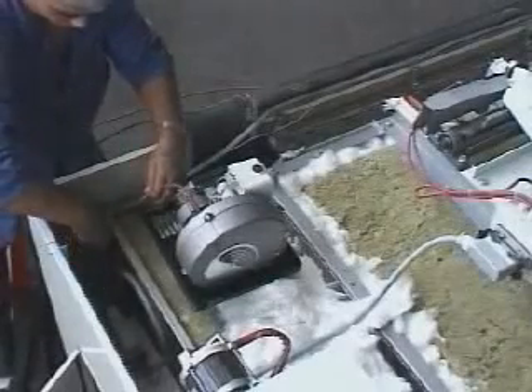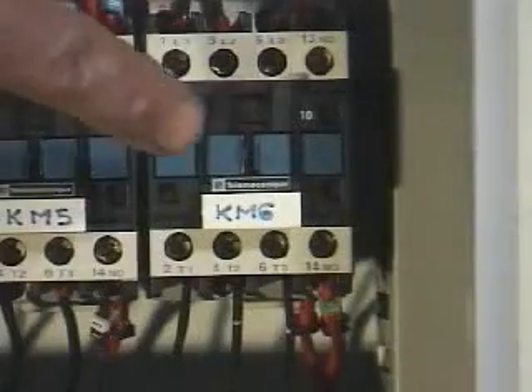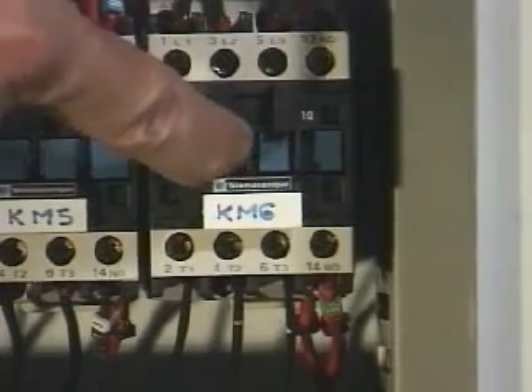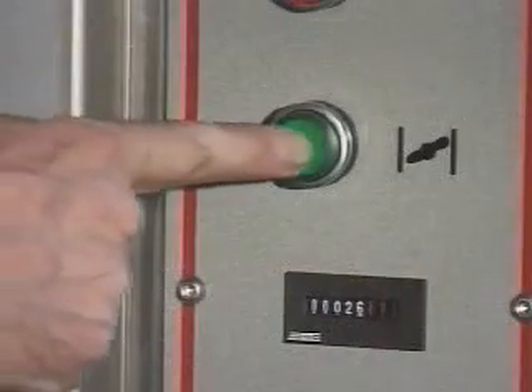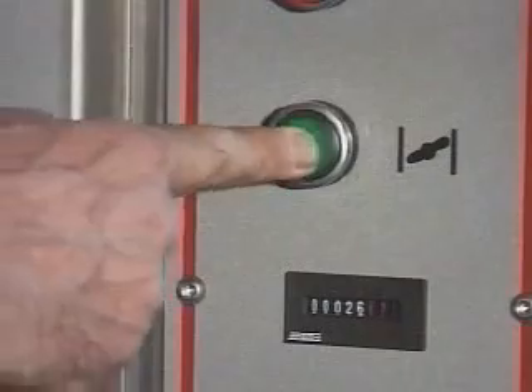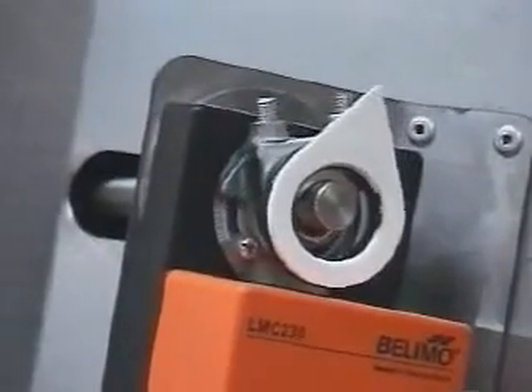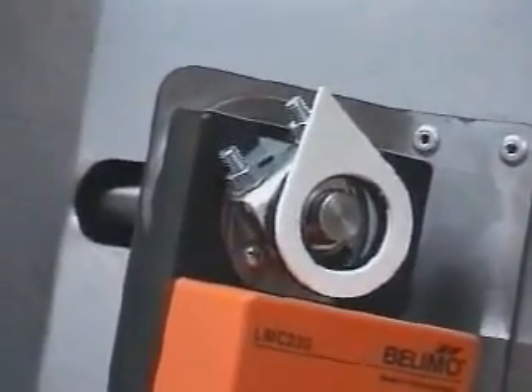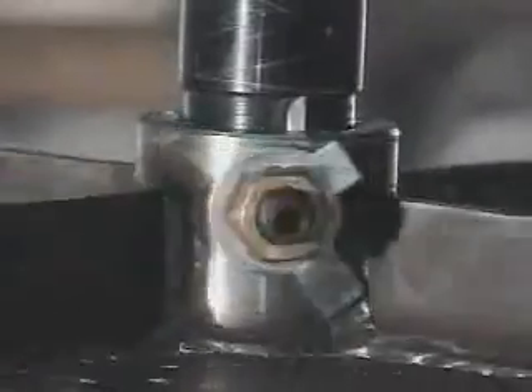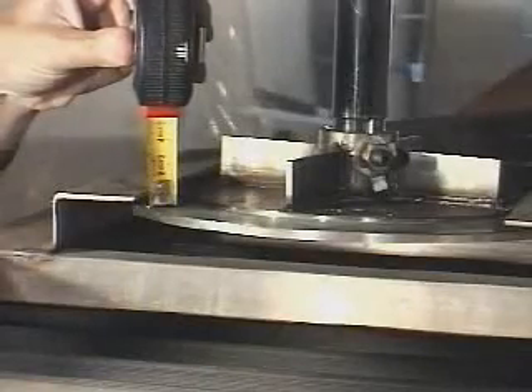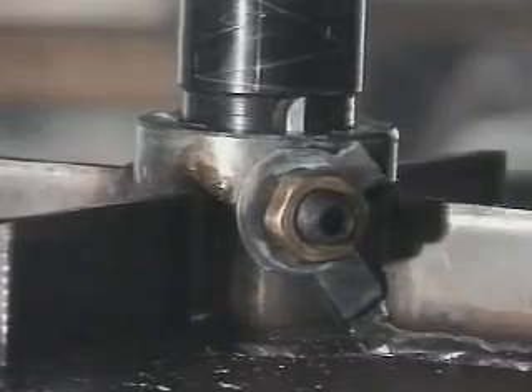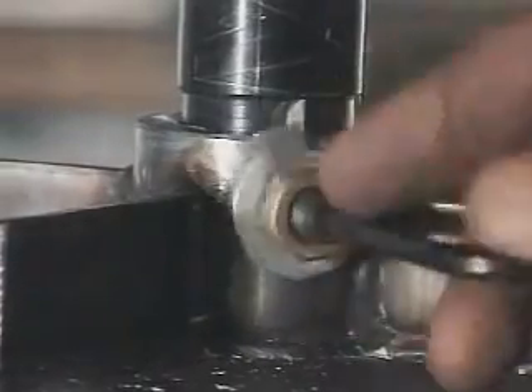Check the rotational direction of the fans by pushing in switch key KM6. If incorrect, invert 2 phases on the main electrical power supply. Install the belt. Also check the rotation of the miniature steam extractor shaft motor. If this is incorrect, inverse the phases with the commutator. Set the play between the rotational disc and the rack suspension system at 3 to 5 centimeters.